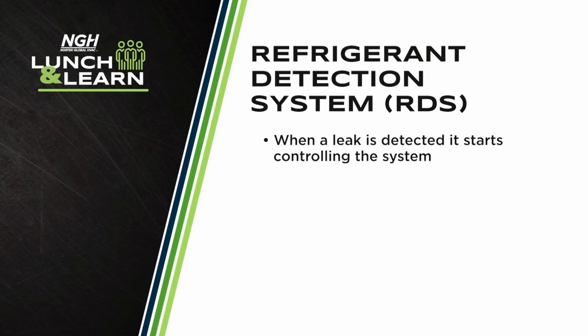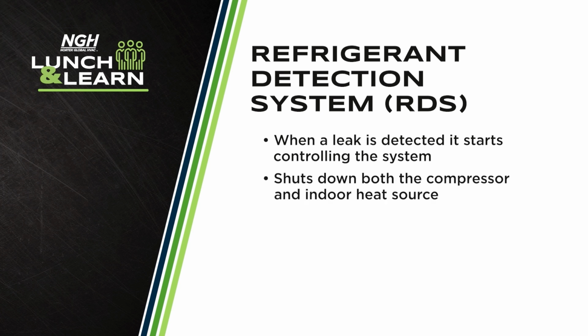You can think of the RDS as sitting in between the system and the thermostat. When a leak is detected, it starts controlling the system instead of the thermostat. The RDS will shut down both the compressor and any indoor heat source. It then runs the circulating blower at high speed for 5 minutes beyond however long it takes for the concentration of refrigerant to drop below detectable levels.